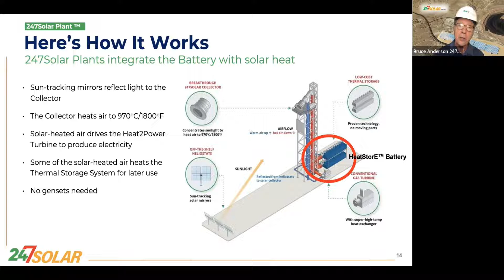No gensets are required in this system. This is much more cost competitive compared with diesel. It's roughly less than half the cost of genset ownership. And the reason, of course, is we're reducing diesel fuel costs, which are expensive, as you all know, by as much as 90%, depending on the location, the design of the system, and the optimization of the whole system against the cost of diesel power and the gensets.